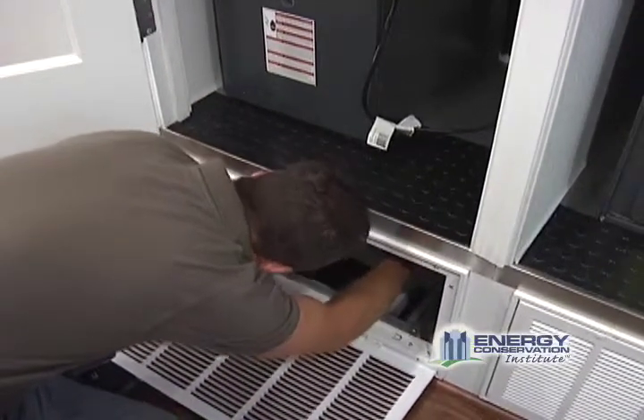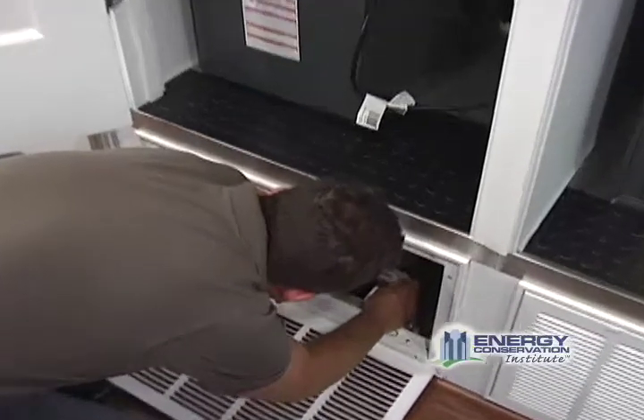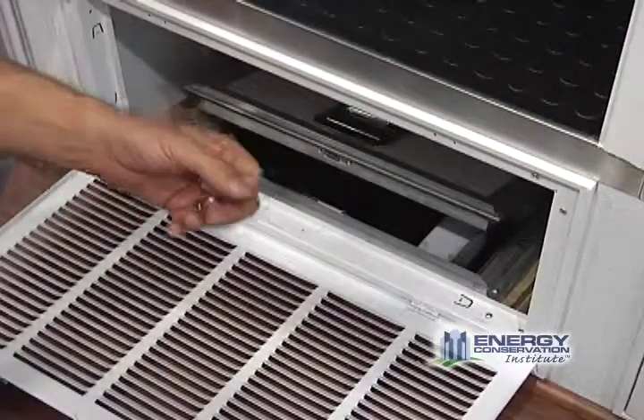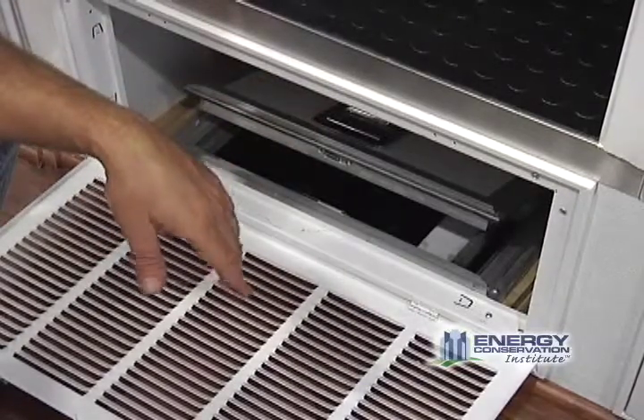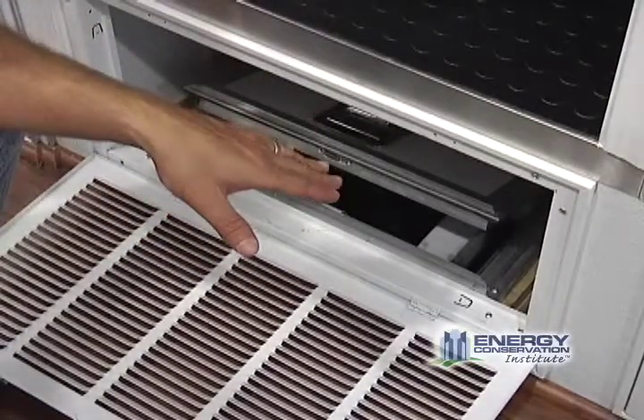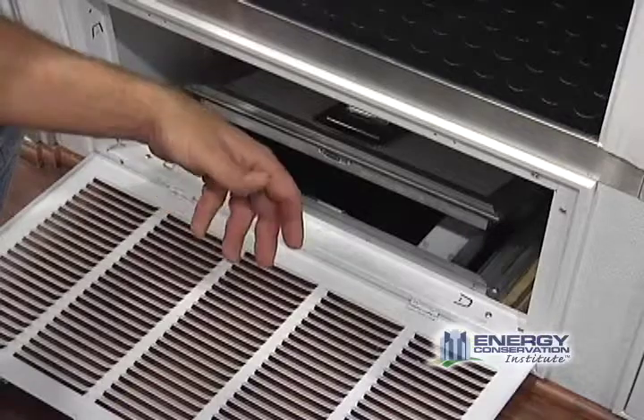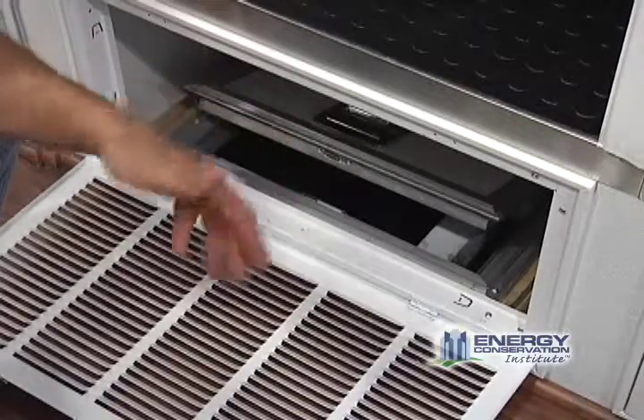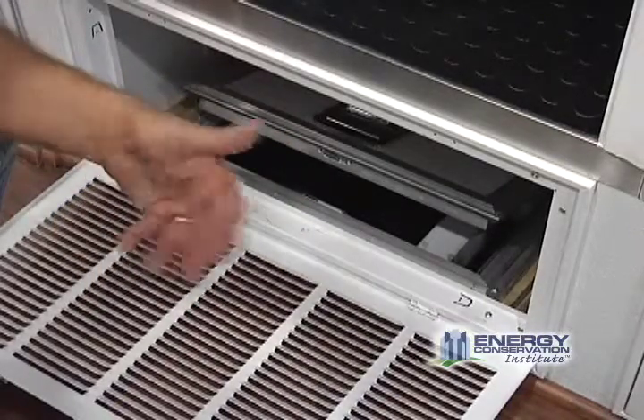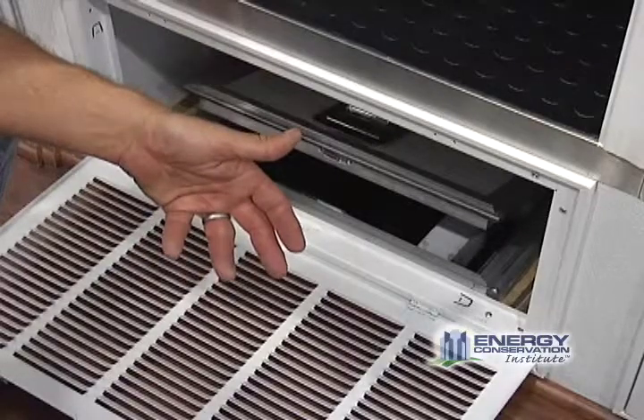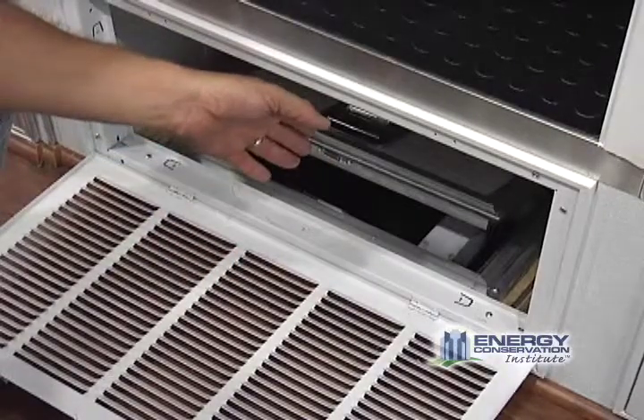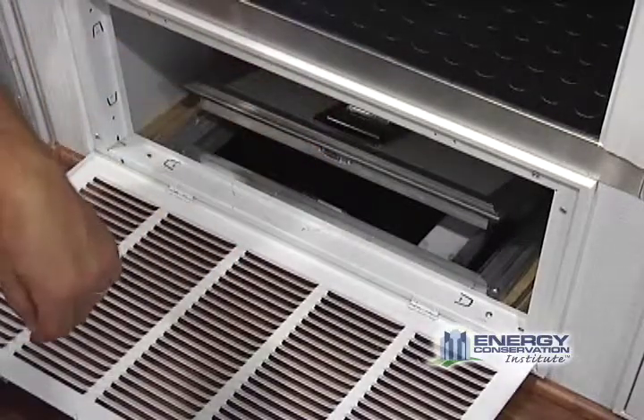So you open up the door and you turn the little knob here mounted on the arm. And the reason this one is adjustable is because you may want to use this system to illustrate the impact of a return plenum leak. In other words, if you want to make the lab go positive because of a return leak, you just open this door and adjust it until you get the pressure that you want.